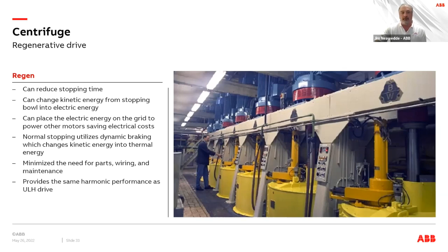The regenerative drives are ultra low harmonic to begin with, so they work great if you've got a cogeneration type facility. A lot of times we see that with sugar processing, where they will have connection to the grid, but they also produce their own energy, and cogeneration doesn't like harmonics. Let's just put it that way. So it is very generator friendly and also works well in a cogen type scenario.